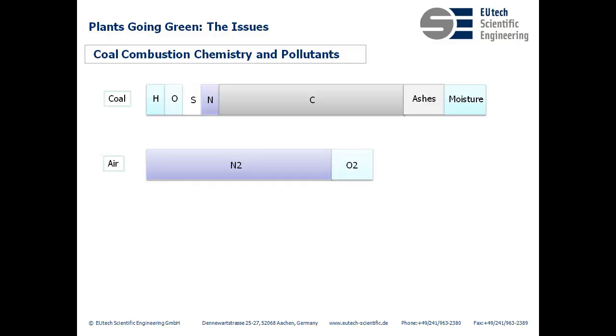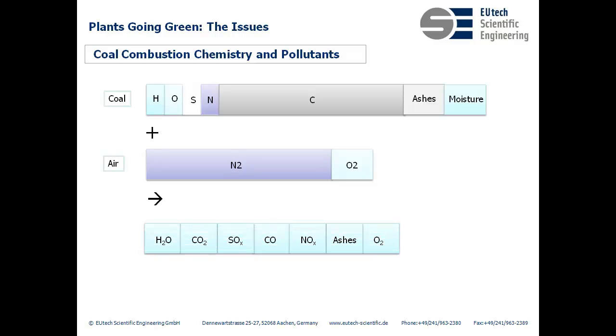For most purposes, air is seen as a mixture of nitrogen and oxygen. The main elements in coal react with both oxygen and nitrogen to produce other gases than carbon dioxide. Unfortunately, most are air pollutants. Here's what the reactions mainly produce: water, which is basically steam; carbon dioxide, which is not toxic and does not have a threshold by boiler guidelines, but reducing its levels leads to benefits; sulfur oxides, which are very toxic inorganic compounds — they react with excess air to produce sulfur trioxide, which dissolves in water, becomes sulfuric acid, and leads to corrosion; flue gas temperatures must be kept above the dew point to avoid this; carbon monoxide, highly toxic and combustible, which increases the boiler's losses; nitrogen oxides, also very toxic and attack the respiratory system directly; and ashes, which affect efficiency via slagging — at very hot temperatures they become too malleable and stick to the walls of the boiler, reducing efficiency.